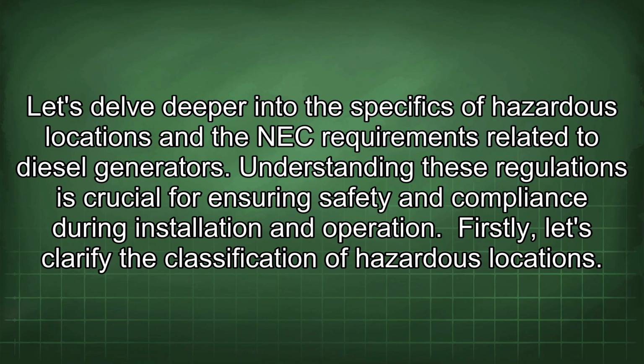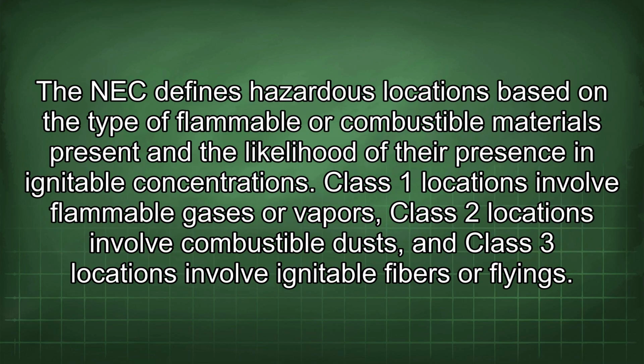Let's delve deeper into the specifics of hazardous locations and the NEC requirements related to diesel generators. Understanding these regulations is crucial for ensuring safety and compliance during installation and operation. Firstly, let's clarify the classification of hazardous locations. The NEC defines hazardous locations based on the type of flammable or combustible materials present and the likelihood of their presence in ignitable concentrations. Class 1 locations involve flammable gases or vapors, Class 2 locations involve combustible dusts, and Class 3 locations involve ignitable fibers or flyings.